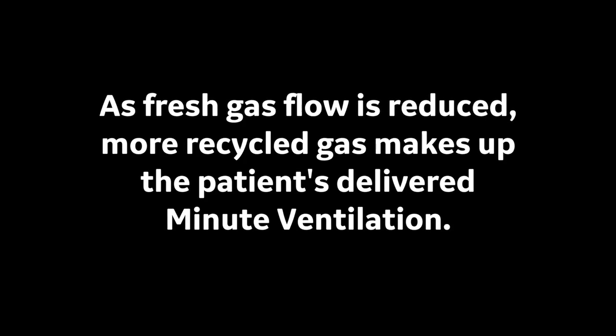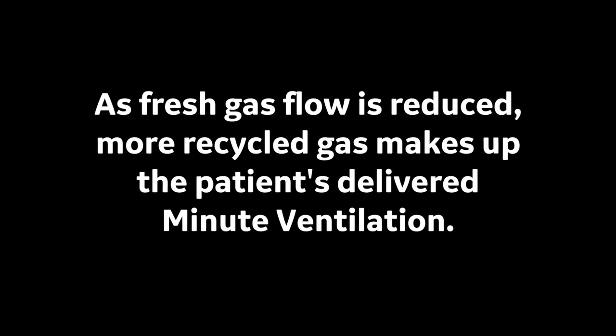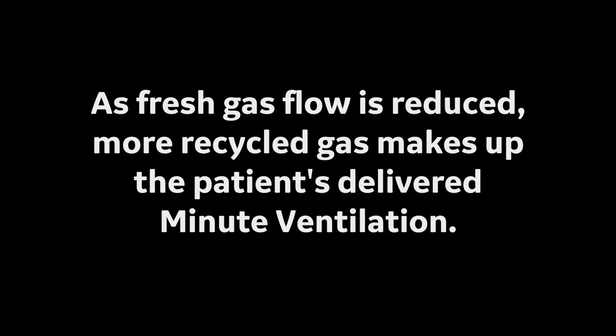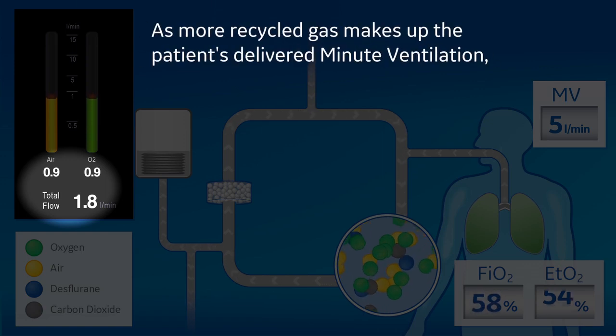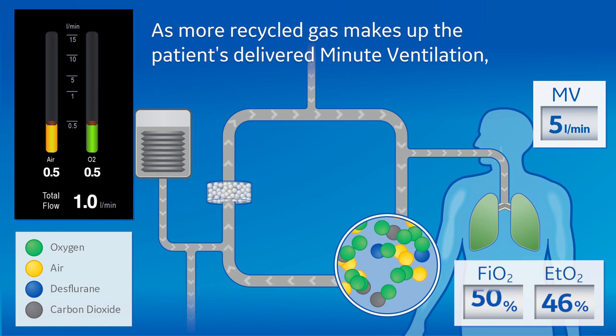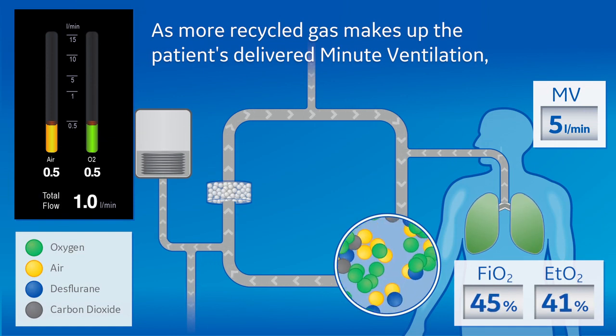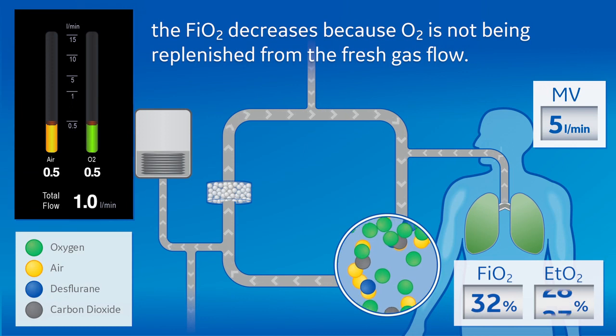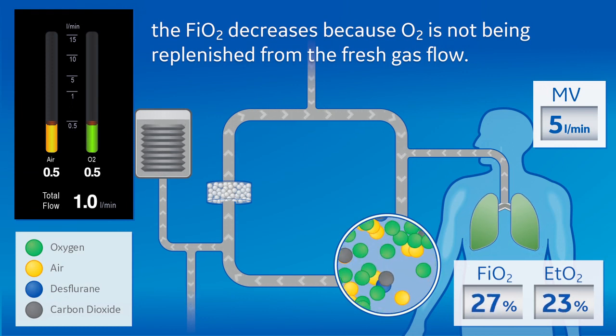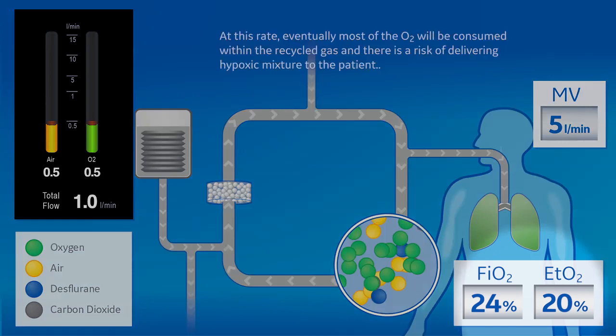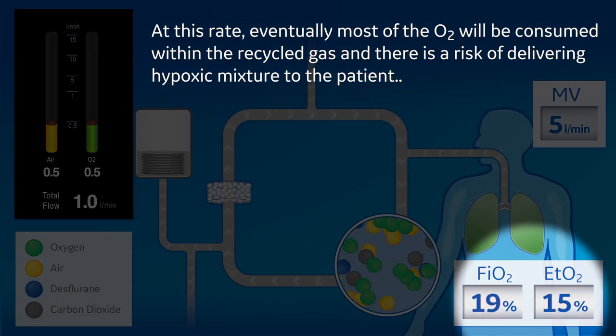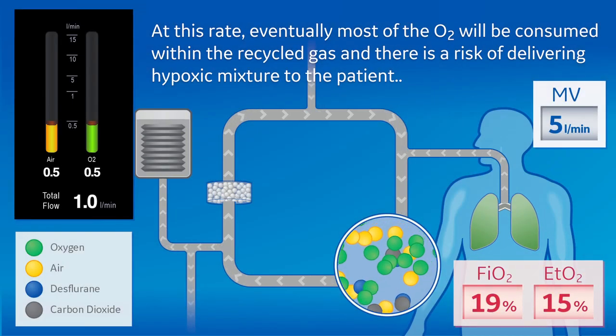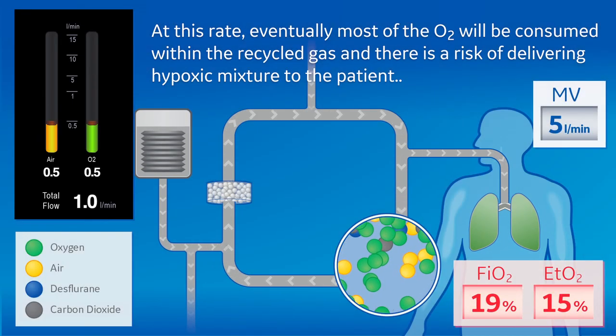As fresh gas flow is reduced, more recycled gas makes up the patient's delivered minute ventilation. As more recycled gas makes up the patient's delivered minute ventilation, the FiO2 decreases because oxygen is not being replenished from the fresh gas flow. At this rate, eventually most of the oxygen will be consumed within the recycled gas and there is a risk of delivering a hypoxic mixture to the patient.